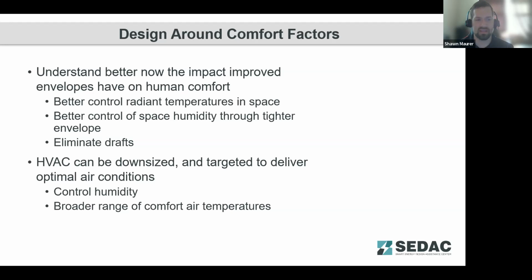And then you're also going to be able to downsize the overall capacity of your HVAC systems and target them to deliver optimal air conditions for humidity and temperature. And you're also going to be allowed a broader range of comfort when you have that balance between radiant temperatures in the space and air temperature.